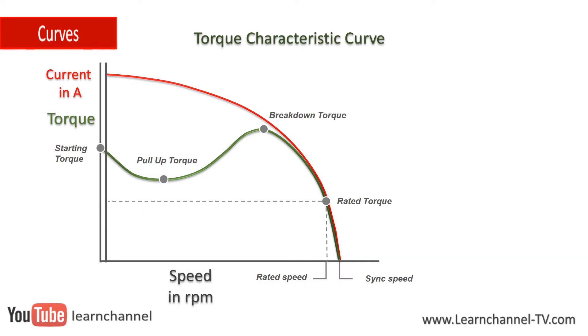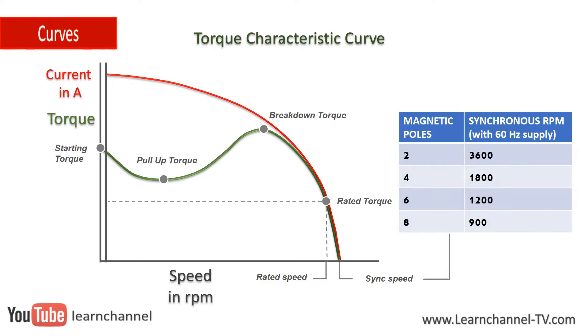The synchronous speed depends on the number of magnetic poles. High-torque induction motors with a high number of poles have a lower synchronous speed. But as the number of poles increases, the cost of manufacturing also increases. So you would perhaps use a motor with two or four poles, but in a bigger size, to get the desired torque.